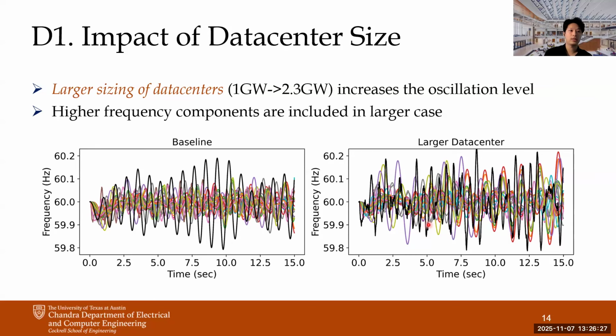Yeah, and now we move on to the data center factors, and the first factor will be the data center size. From the baseline case, we assume that there is a smaller number of data centers, but with a larger size for each, resulting in the same penetration level. So we modify the size of the data centers from 1 gigawatt to 2.3 gigawatts. Accordingly, in the larger data center case, there's a larger oscillation magnitude, but the more notable observation is that higher frequency components are observed in this larger data center case in the right figure. So this could be interpreted that the individual data centers inject their own higher frequency components into the grid frequency.